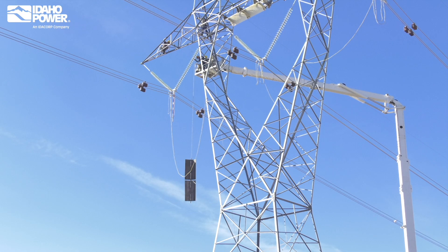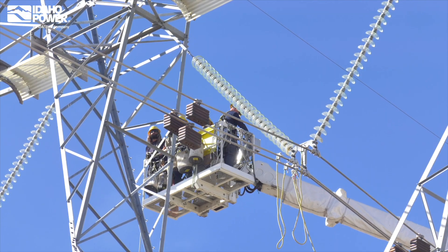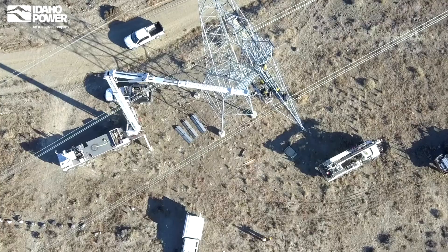So why is this project necessary? Birds like to roost on our structures at night — ravens and eagles, other birds of prey — and their excrement can cause contamination of the insulators and can cause faults on our line. Poop is a great conductive material, so it gets on our insulators and compromises them, and they lose their insulative properties and the line can trip when that happens.